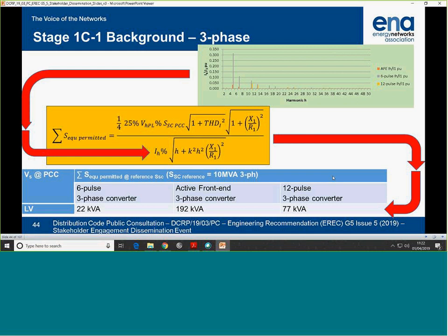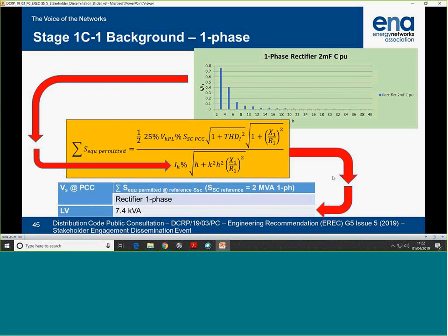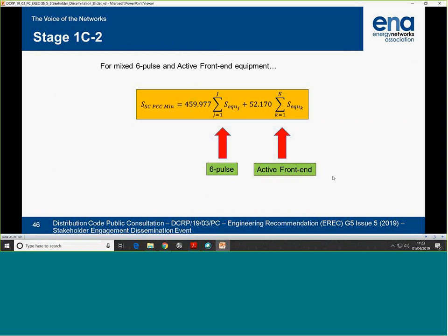The other background to that is it's assuming 5 items with a coincidence of 0.9. So 5 times 0.9 is 4, so I put 4 in the formula. It's assuming you could connect other items to the network at this stage of assessment, if not your whole planning level at this stage. Single phase is similar, but you're assuming fewer items, so there's a 1/2 in that equation. 1/2 was the case of mixed equipment. In this case, we're using the equipment ratings, multiplying them by the factor, which effectively gives us the ratio of fault level to rating. So there's two.